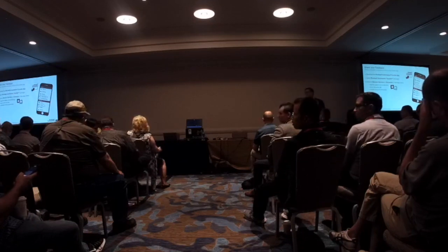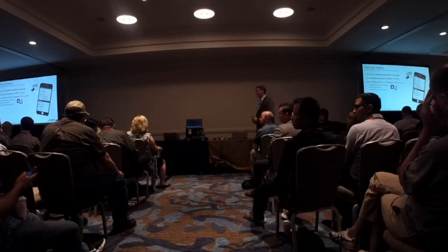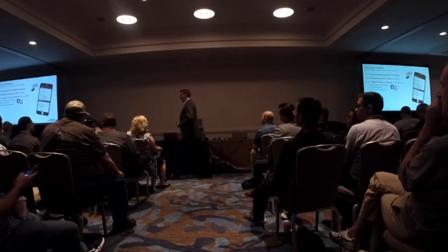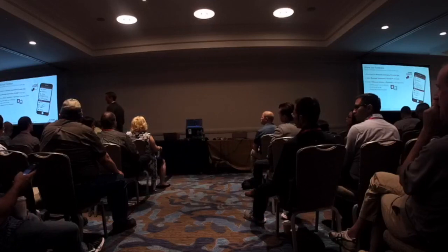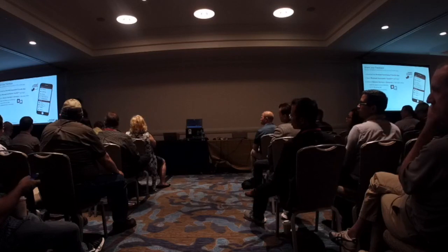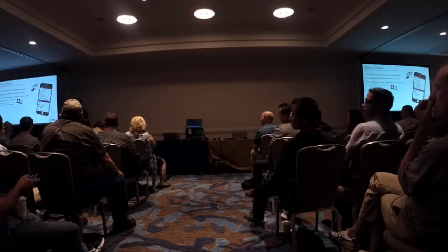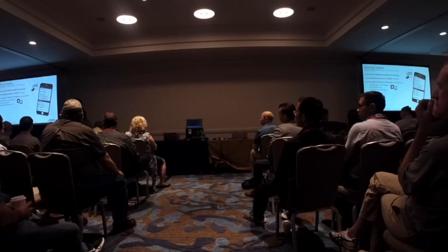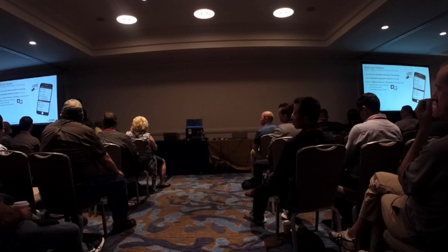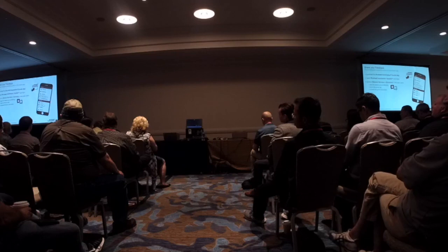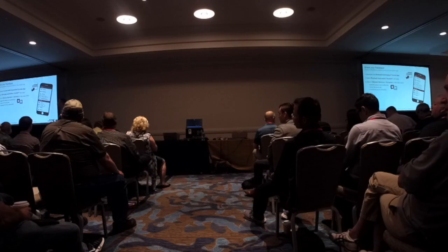With FactoryTalk Gateway, I don't need KEPServerEX anymore? So KEPServer remains a core part of our architecture. With KEPServer, we're focused around using that to interconnect across other protocols. So if you're going to a third-party DCS system and there's a specific protocol of communication, then you would leverage the Kepware server software. If you're producing data or consuming data over OPC UA specifically, that would be where you would use the FactoryTalk Gateway.